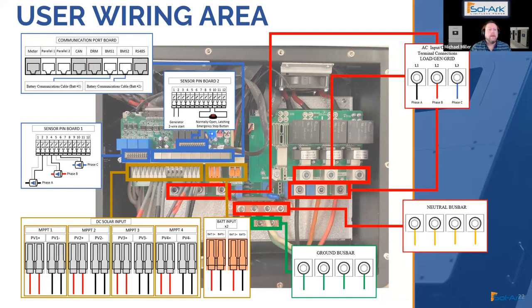Again, the 2-wire generator start, and the other pin board is for the CTs. This is going to be a lot easier than trying to wire together 15 Ks on each phase. All the CTs will be in one place. It'll be very clear which phase goes with which input. So on the bottom left, we have all the solar inputs, as I mentioned, 4 of them, but you have 2 places to land on each of those MPPT trackers. So a lot of flexibility there. The battery inputs as well, now we're down to 4-gauge wire because we have high voltage batteries. So that's going to be some ease of working with the wires and time savings. To the right side, we have all the AC inputs, right and bottom. Essentially, that gen port, as I mentioned, is where the EV charger could land. It's very clear where everything goes, and it's a familiar platform with the other products that we have. So your installers should find it easy when transitioning from a 15K to a 30K, for example, or a 60K.